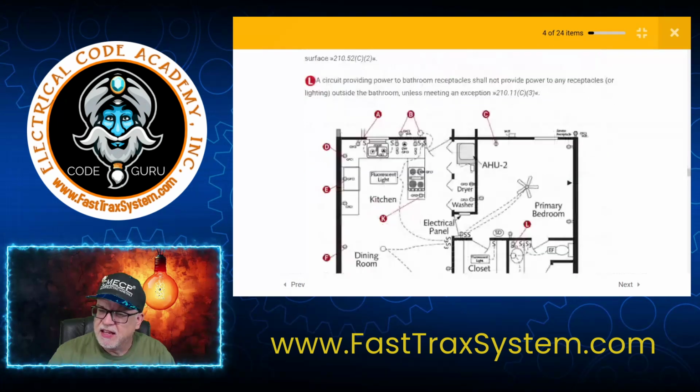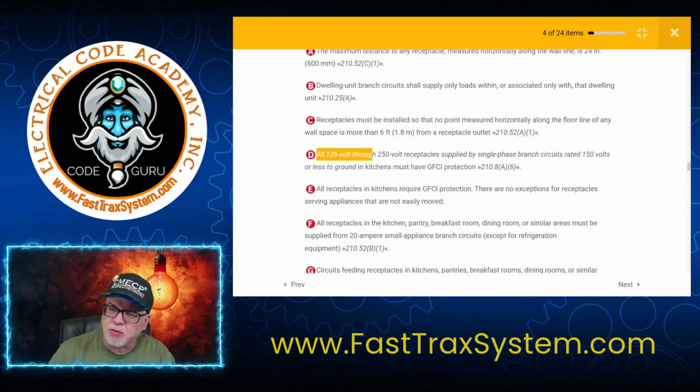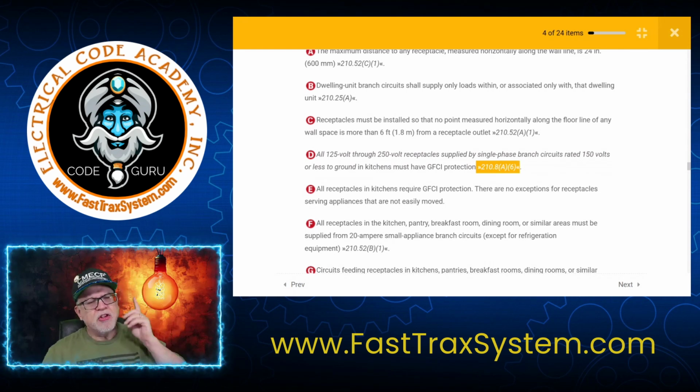So let's go down here to A. And here it's calling out right here on the countertop. It's talking about the spacing, right? And then it'll have another callout for D for this receptacle. So let's see what that's about. D. It says all 125 volt through 250 volt receptacles supplied by a single phase branch circuit rated 150 volts or less to ground in kitchens must be GFCI protected. And it gives you the code reference.